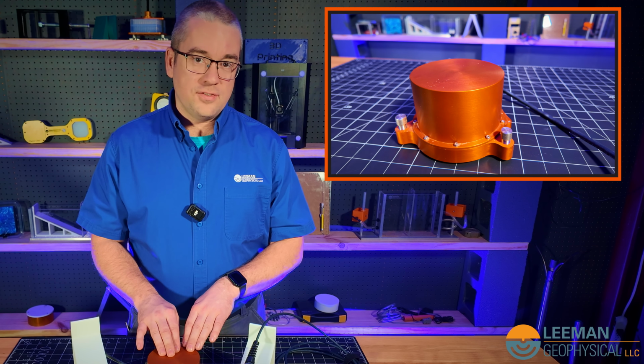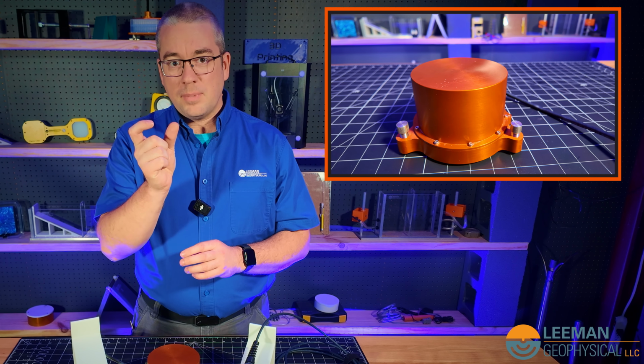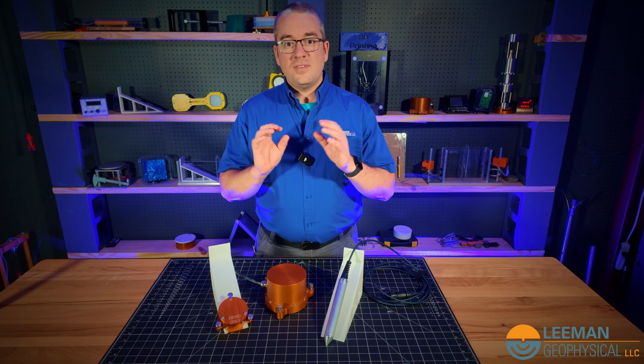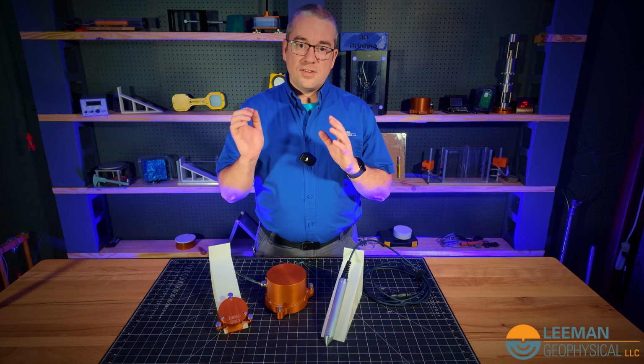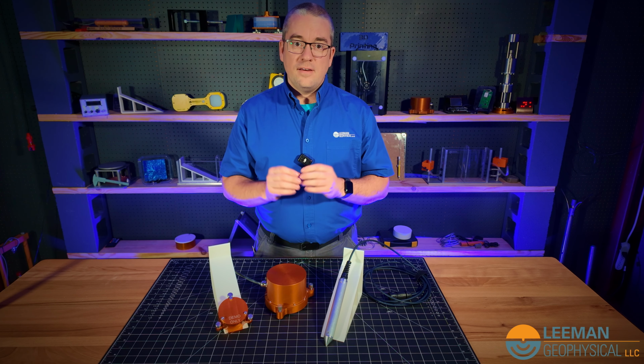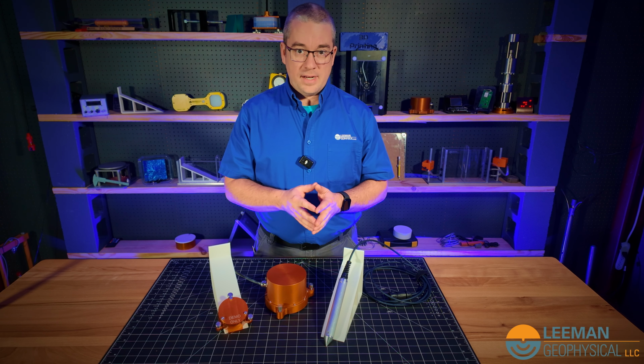So an electrolytic sensor uses pretty much a bubble level. It looks like a bubble in a bubble level that you would have at home to level pictures on the wall, except it's very accurate and it has electrical wires running through it, and we can measure the position of that bubble very accurately, which lets us have resolutions of down into the nanoradian range.